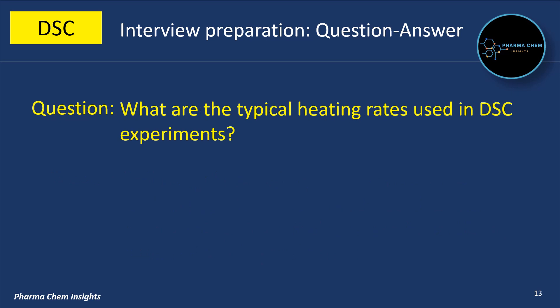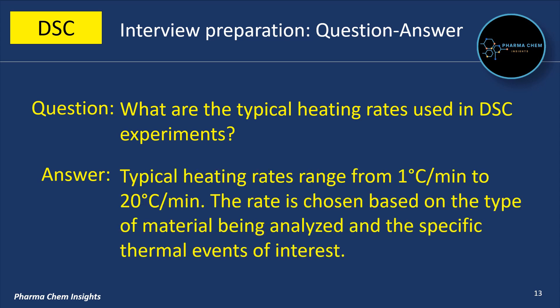Next question: What are the typical heating rates used in DSC experiments? Typical heating rates range from 1°C per minute to 20°C per minute. The rate is chosen based on the type of material being analyzed and the specific thermal events of interest.